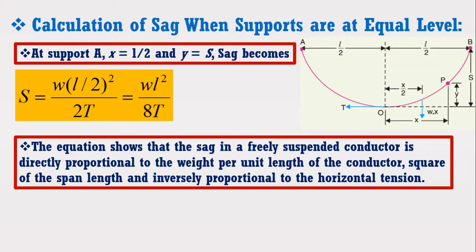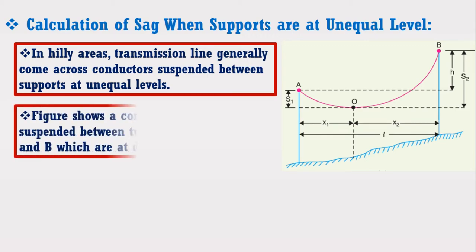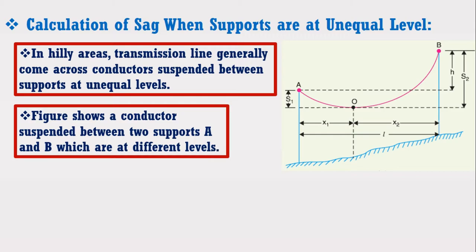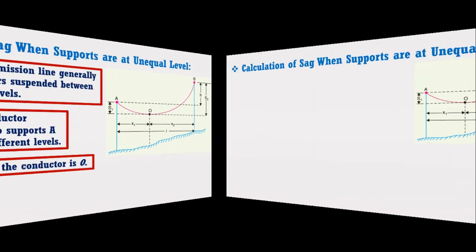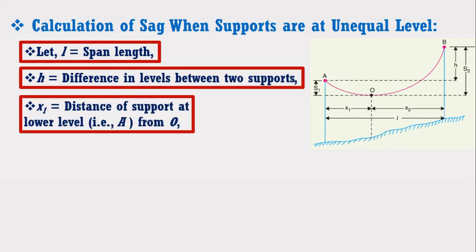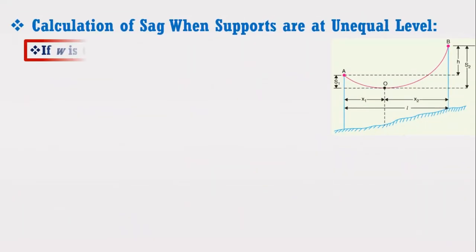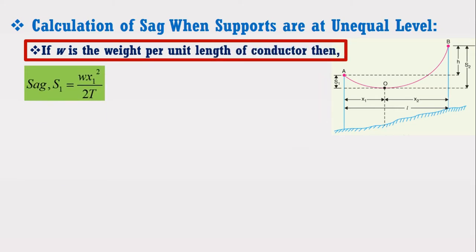Now I am going to derive an expression for sag calculation when supports are at unequal levels. In hilly areas, transmission lines generally come across conductors suspended between supports at unequal levels. The figure shows a conductor suspended between two supports A and B at different levels, with the lowest point O. Let L be the span length, H be the difference in level between the two supports, X1 be the distance of the lower support A from O, X2 be the distance of the higher support B from O, and T be the tension in the conductor. If W is the weight per unit length, then sag S1 equals W X1 squared upon 2T, and sag S2 equals W X2 squared upon 2T.